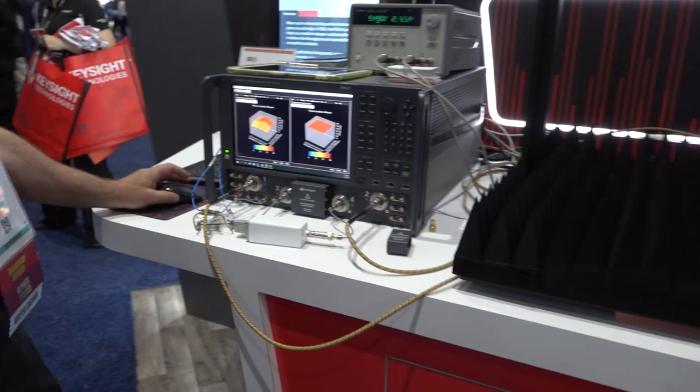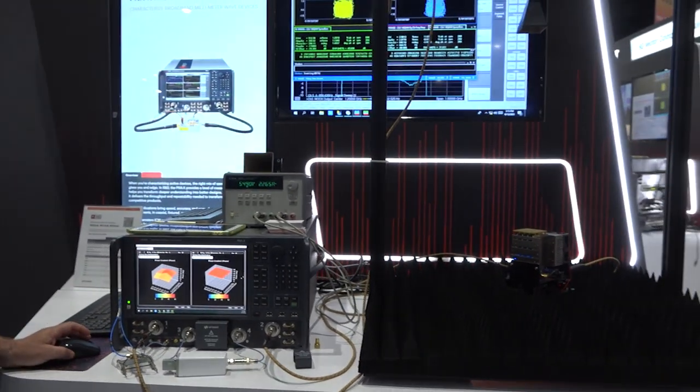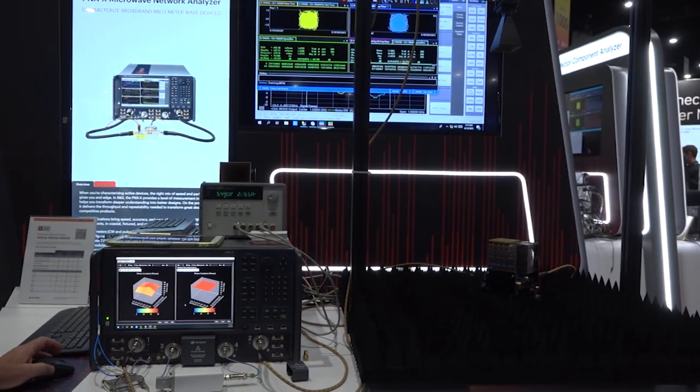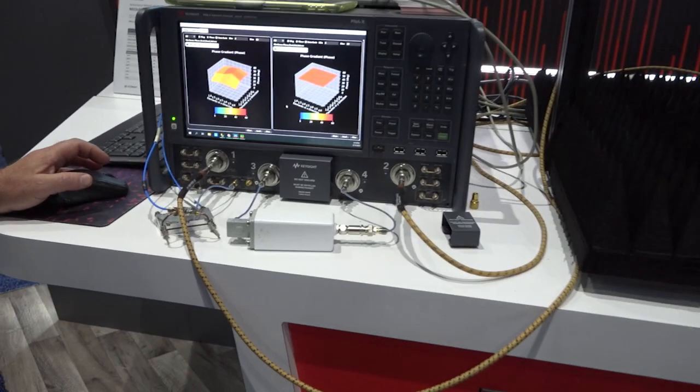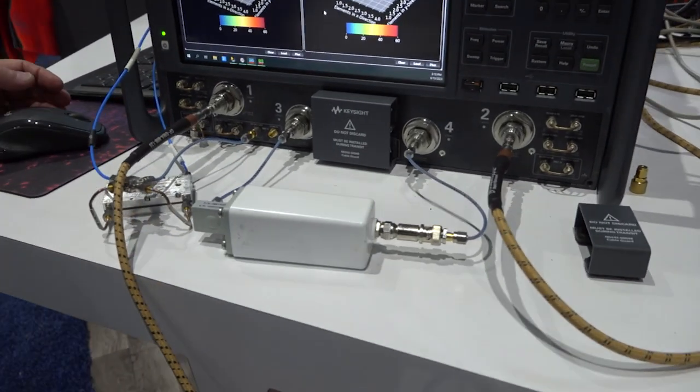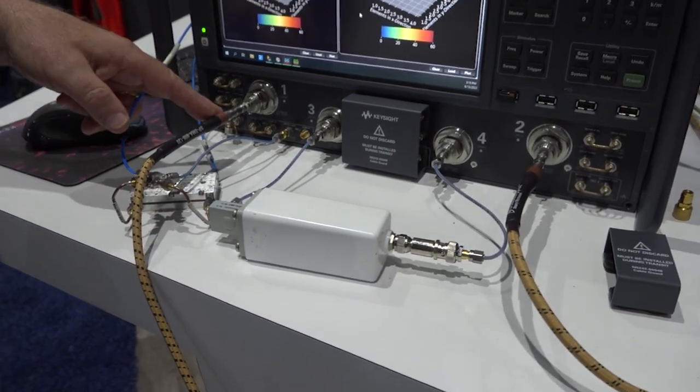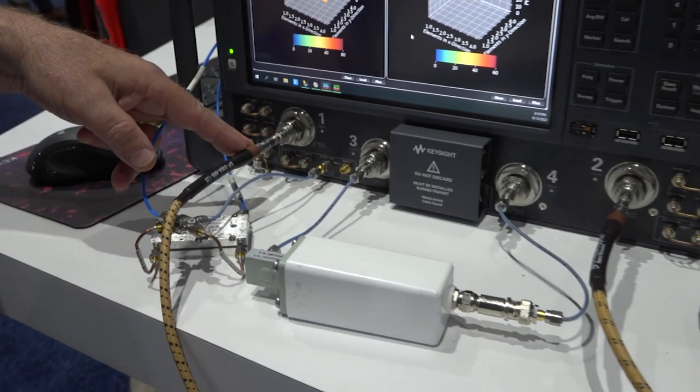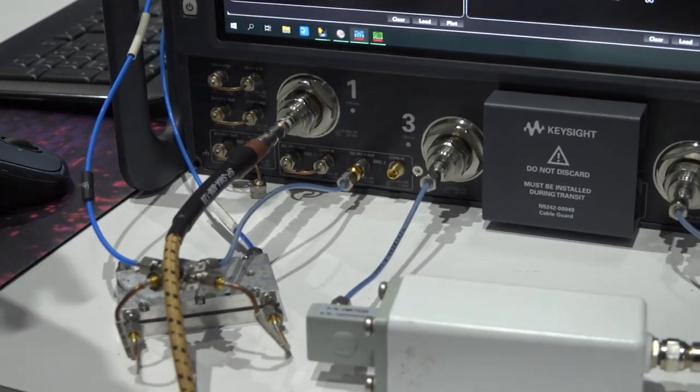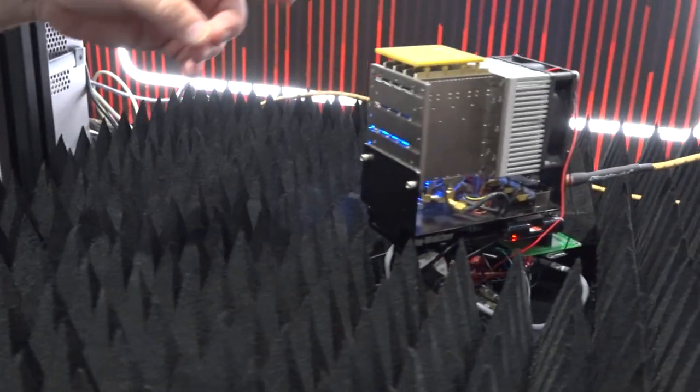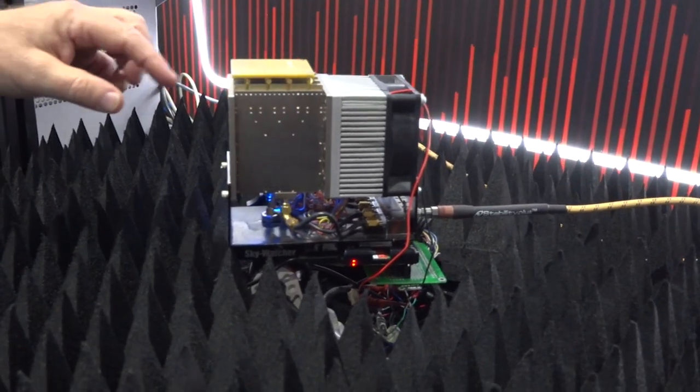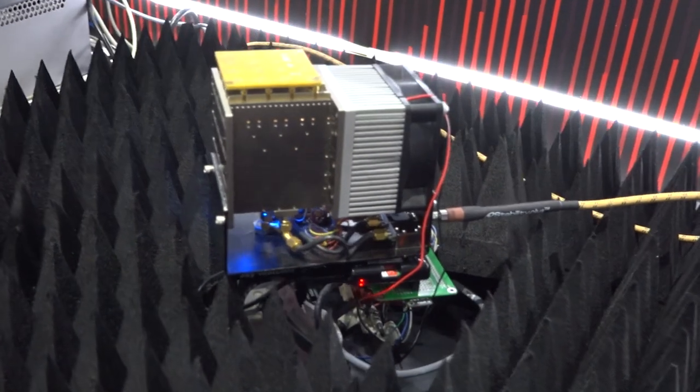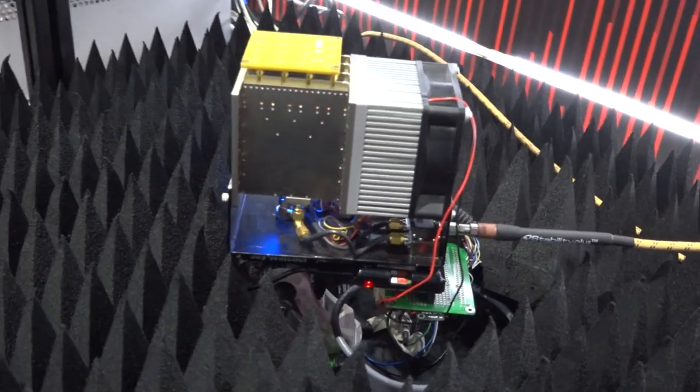The second demonstration is quite interesting. We're showing down here on the lower side the ability to characterize and calibrate phased array antennas. The first port is going to the reference horn and the second port is going to the phased array antenna. This phased array antenna has 16 elements and they're intended to be all perfectly aligned but they're not perfectly aligned.